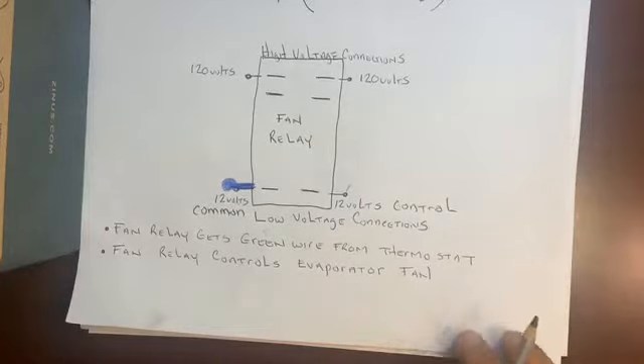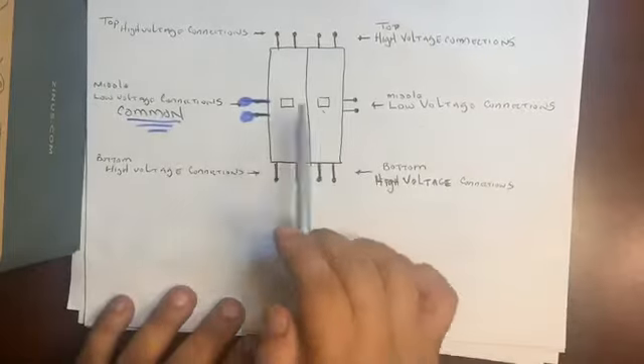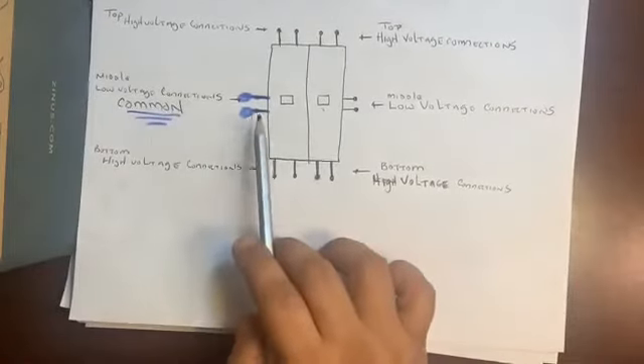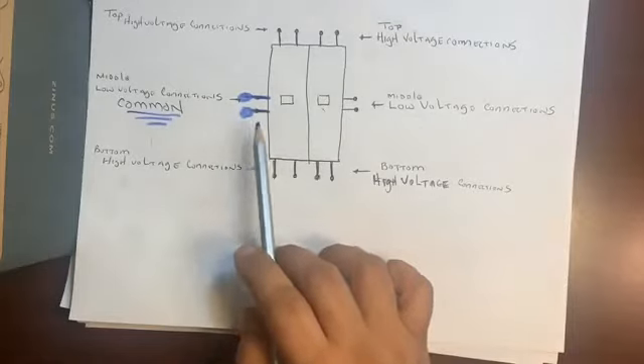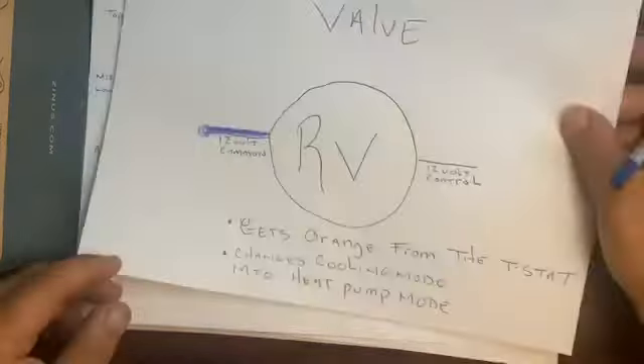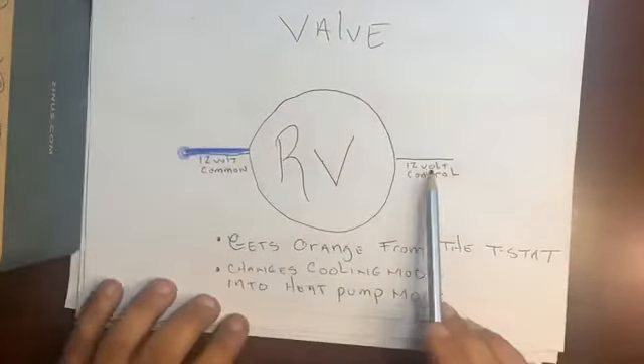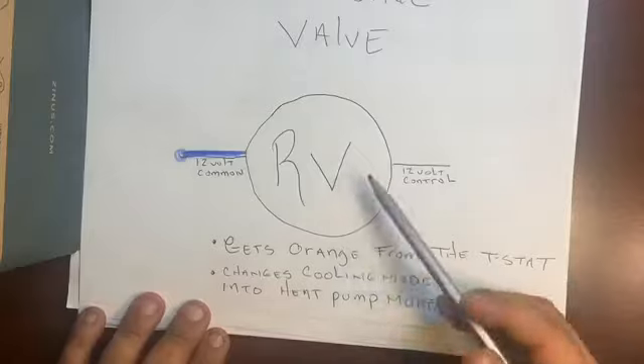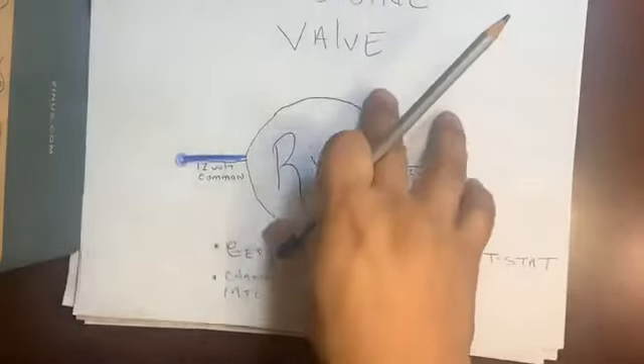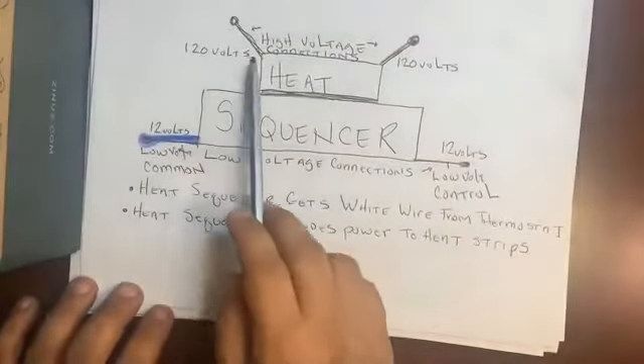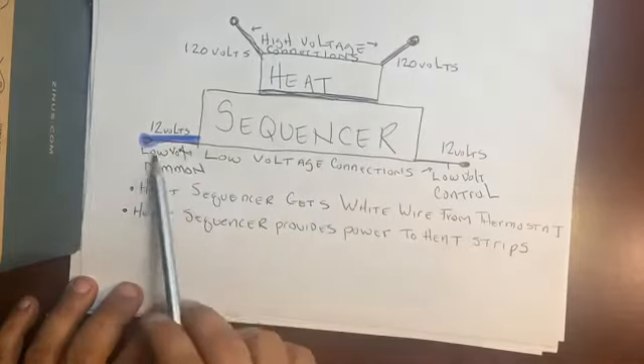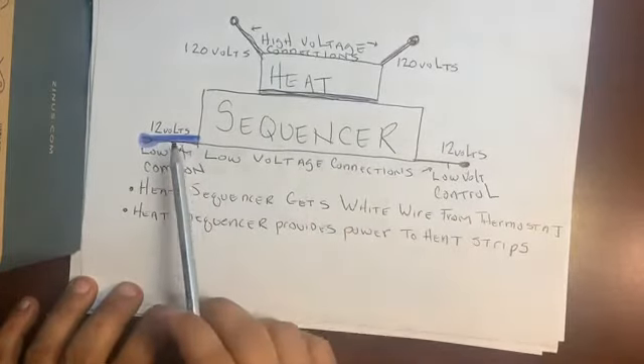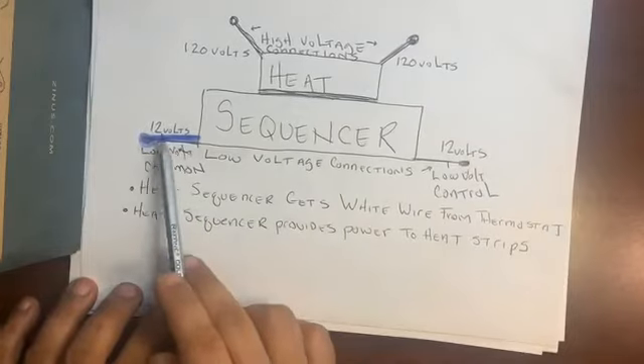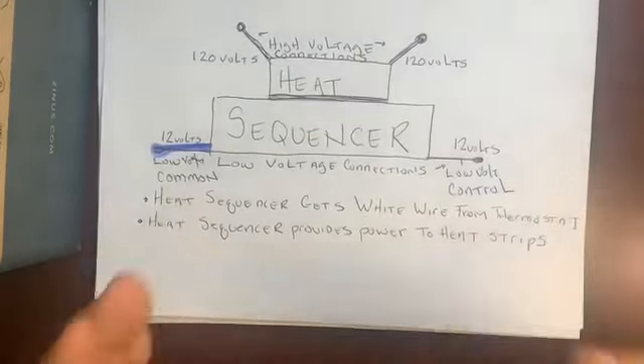So going over our relays, fan relay for the indoor fan motor inside the air handler. Compressor contactor, low voltage connections in the middle, common on the left, outside condensing unit to power up the compressor and the condensing motor. Reversing valve, 12 volt common, 12 volt control, gets orange from the thermostat, changes the system from cooling mode into heat pump mode. This is outside at the condenser. Finally, our heat sequencer gets the white wire, 120 volts, connections along the top, low voltage 24 volt connections on the bottom, low volt common is blue. These are our basic relays. Now let's put them on the board.